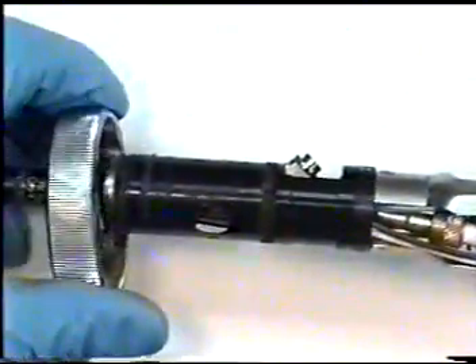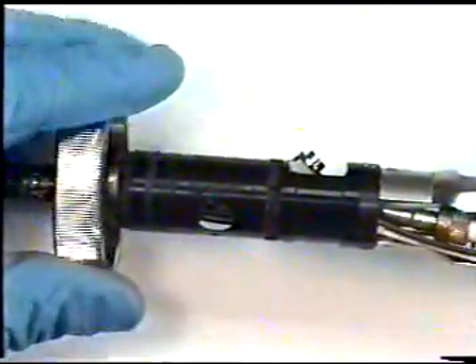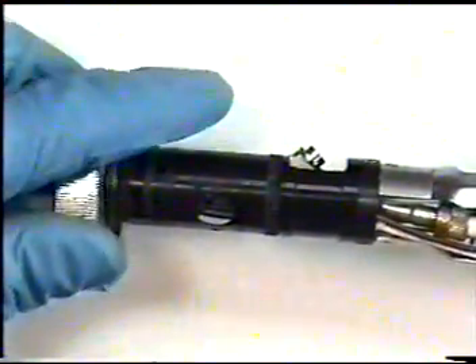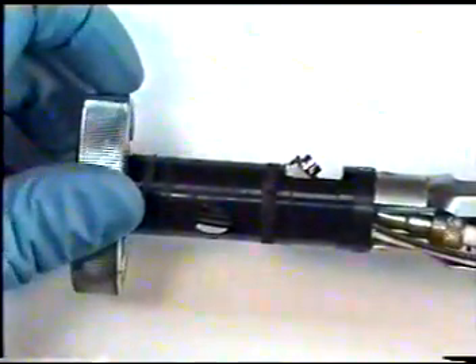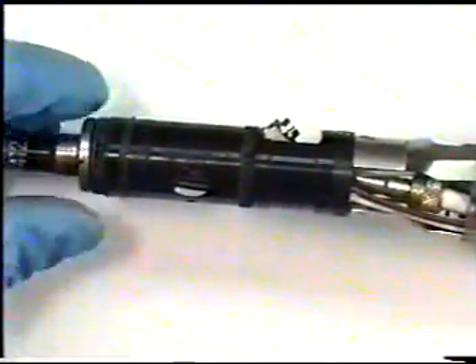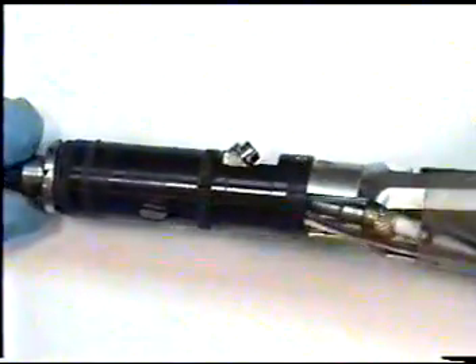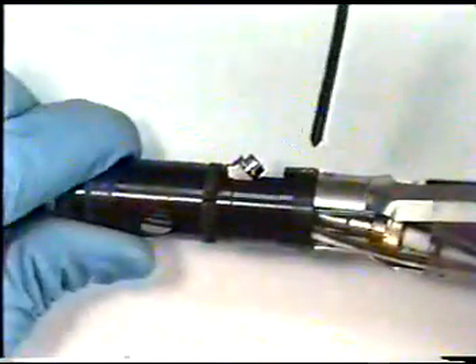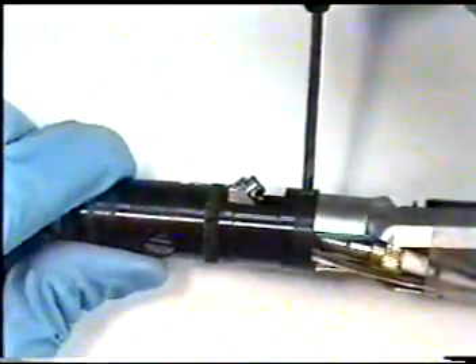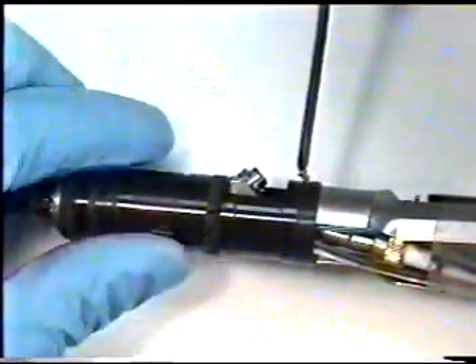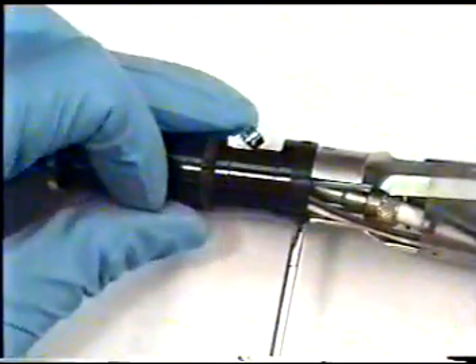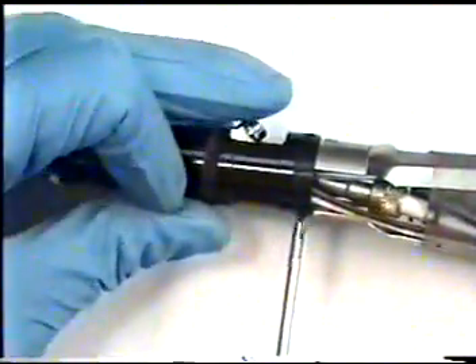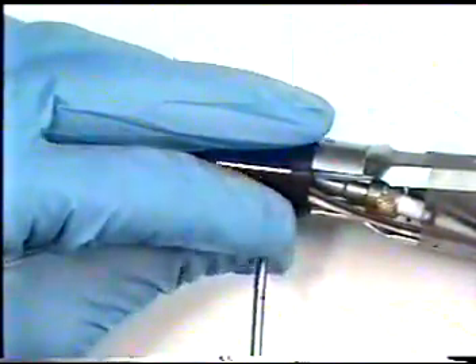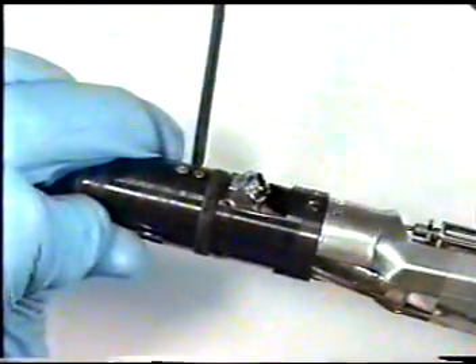Using your insertion tube C-tool wrench, unscrew the locking ring counterclockwise to loosen and remove locking ring. Loosen ring finger tight, but don't remove completely until we remove all the stainless steel screws from control body section. Using your Phillips head jeweler screwdriver, remove all screws from the black control section, including the 2 screws which hold in your biopsy forceps valve assembly.